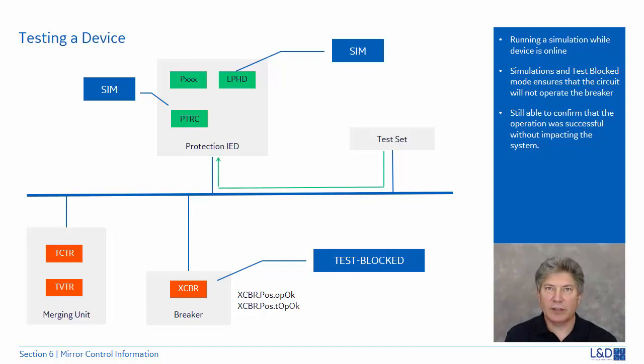A test set will send a sample value with the same identifications as the ones normally received by the protection IED but with the simulation flag set to true. The protection IED will now receive the sample values from the test device and will initiate a TRIP.